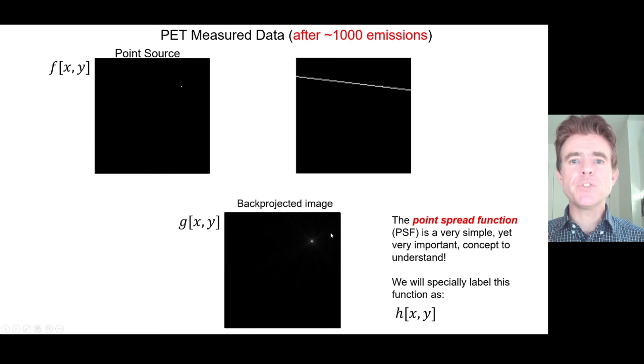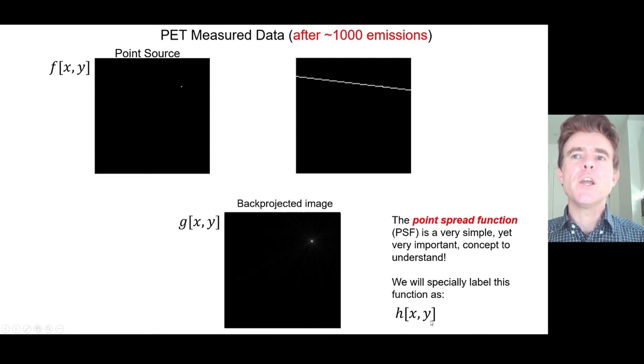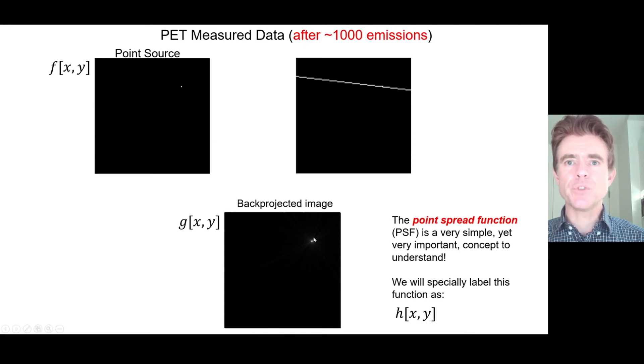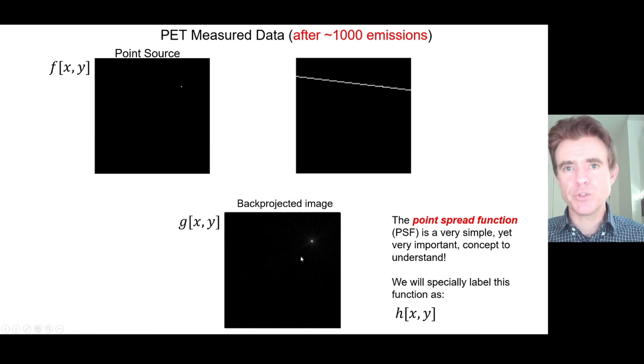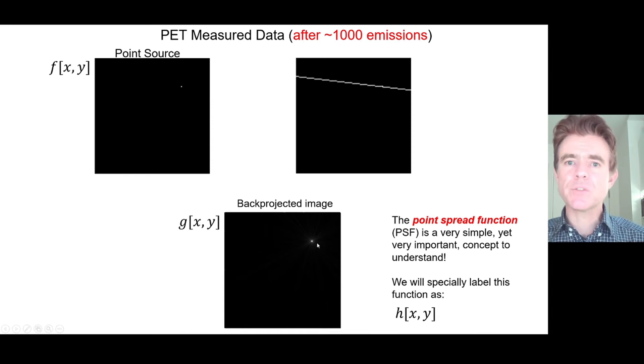We label that response as the point spread function and give it the function name h — the kernel, the point spread function h as a function of x and y. Normally for the PSF to be practical, we'd place the point source in the middle of the field of view to capture this response centrally and capture as many of the tails as possible, since this spreads from minus infinity to plus infinity, or at least the dimensions of the matrix. The key idea is that a point source has been replaced by a point spread function in the back-projected image.